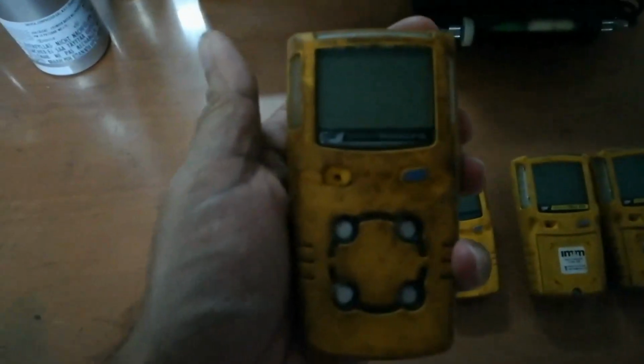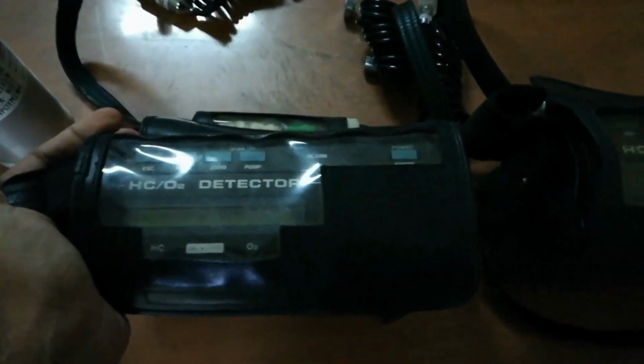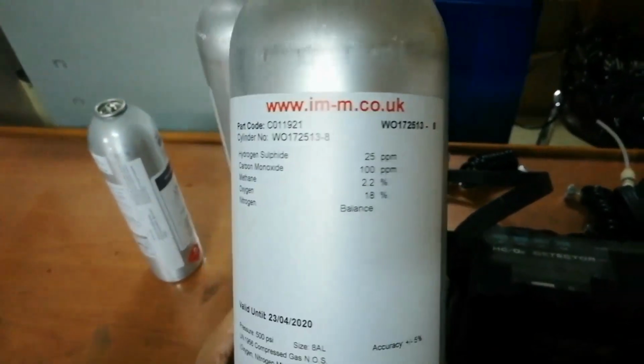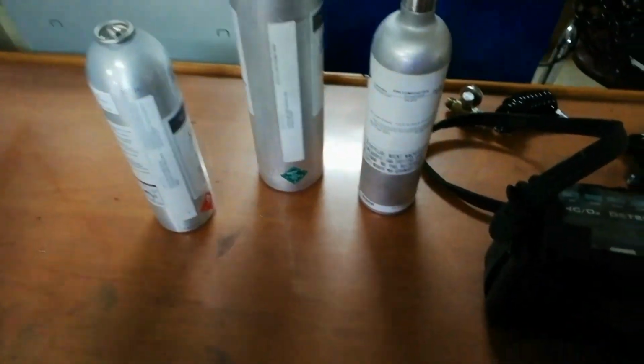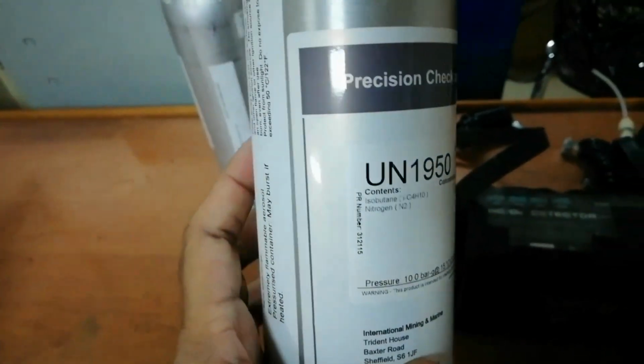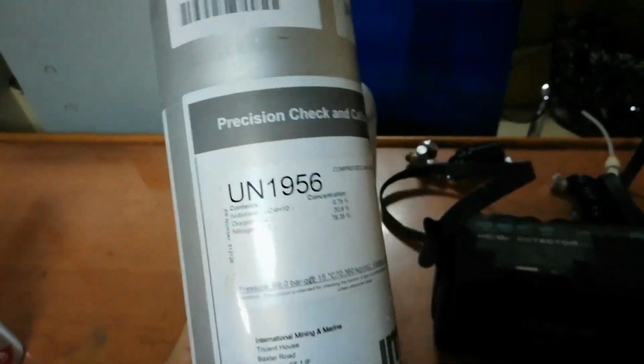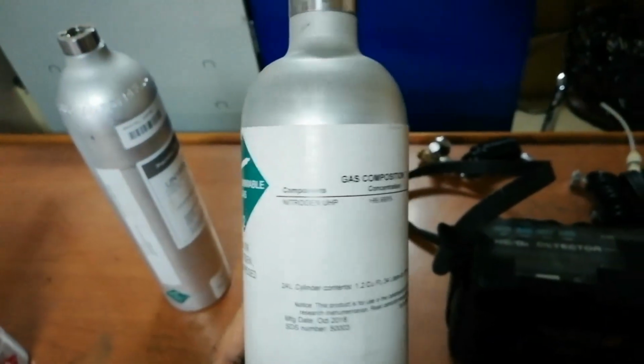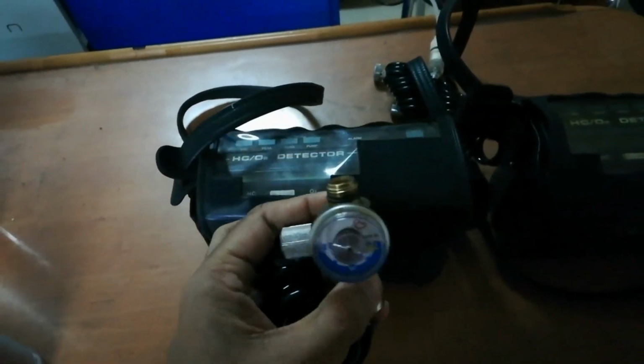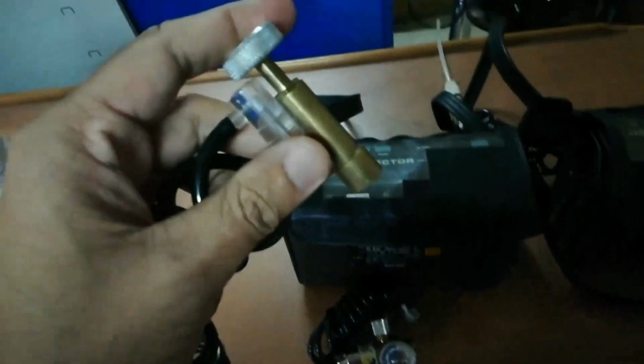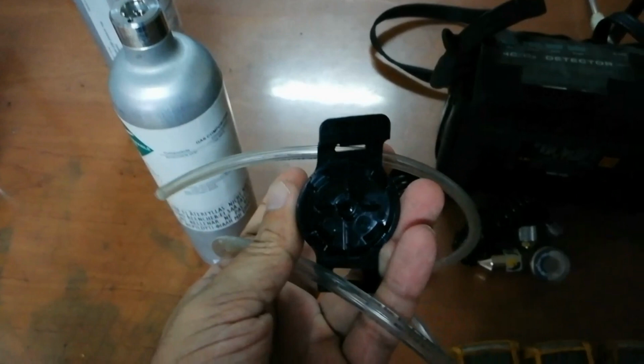Here we have four sets, and you can see I have these Recon RX 415 oxygen and flammable gas monitors. I have two pieces for all operations. I am using four types of span gas, and I will explain briefly once we are doing this calibration test. This one is isobutane 8%, and this one is also isobutane and oxygen balanced in nitrogen, and this one is 100% concentrated nitrogen. Here we have a 0.5 liter per minute fixed regulator, and we are also using an adjustable flow regulator set to 0.5 liter per minute. This one we will use for the multi-gas detector.